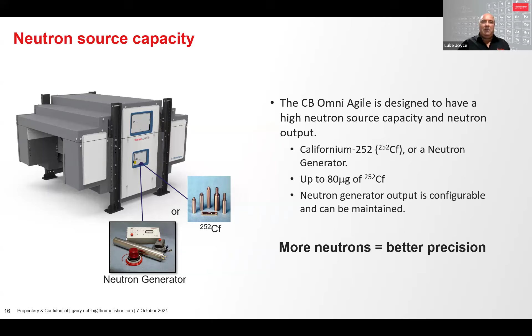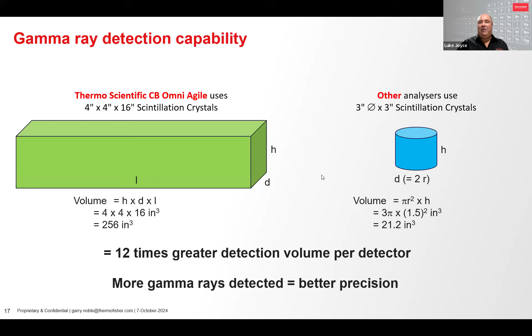So the neutrons are needed to produce the gamma rays. However, once you've produced them, you've got to detect them. So Thermo Fisher Scientific PGNAA analyzers use a 4x4x16 scintillation crystal. Some other PGNAA analyzers use 3-inch by 3-inch cylindrical crystals. Just from the volume calculations, you can see that the larger crystal is up to 12 times larger in volume. Larger detectors can detect more gamma rays, and the more gamma rays you detect in a given time frame, the better the precision.